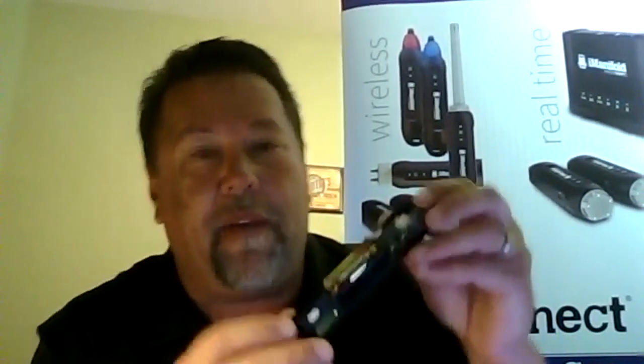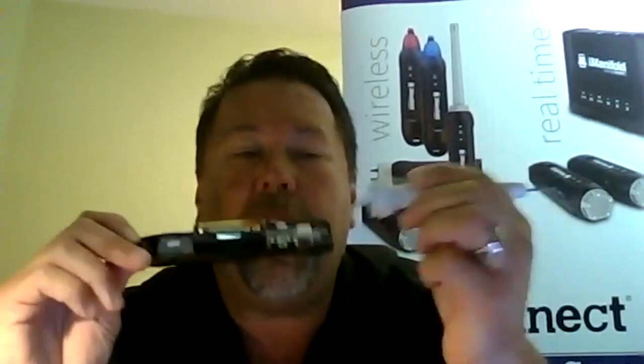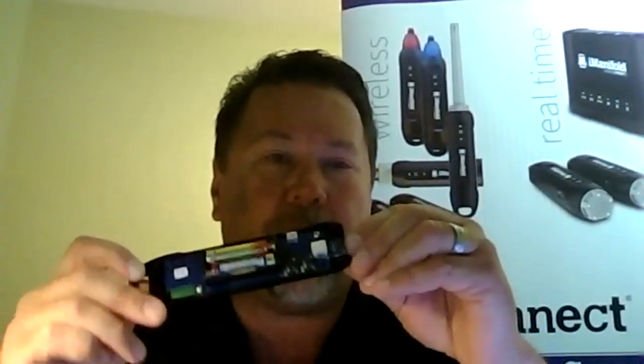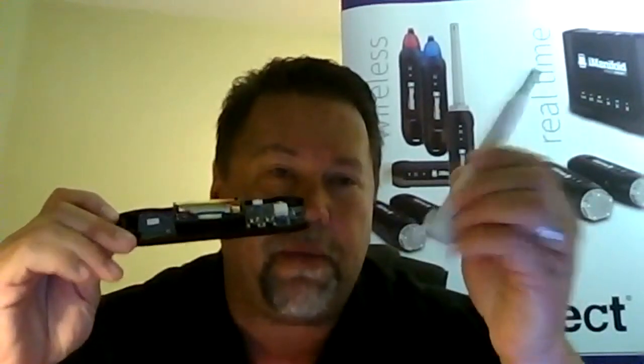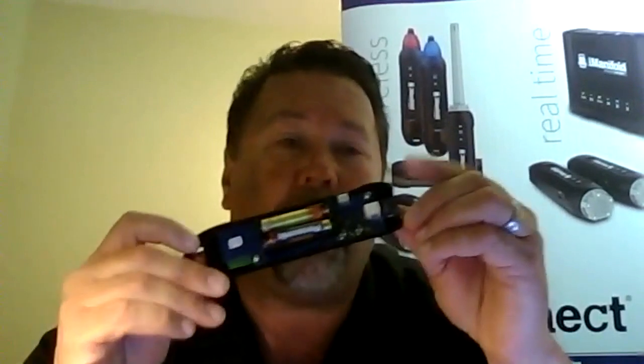Now, on some of the older units here, I want to show you that on the other side of this board, there's a small reset button. On this particular one, we don't have it. On these newer ones, there is no reset. It's just the fact that this thing will pull off. So if you're having an issue and it's not the daughter board, contact us. I'll do a little field check on it real quick. And then it could either be that the tip needs replacement or the motherboard needs to be replaced. But on the older systems, if you have generation 1 probes that have a serial number that begins with A10, on the back of this little board, there's a little tiny switch, and you're going to cycle the switch a couple of times, and the switch needs to be put in the outbound position, and that'll reset that board.